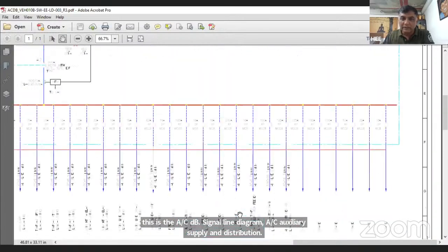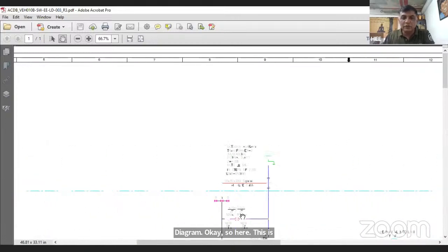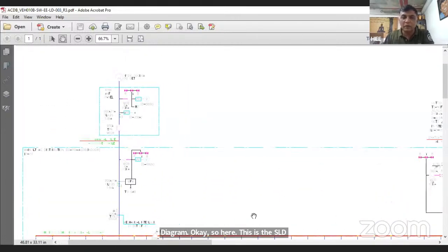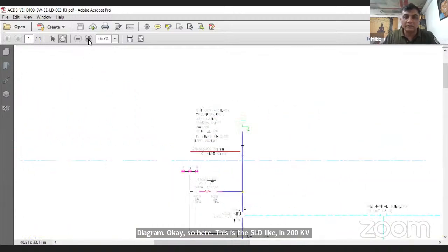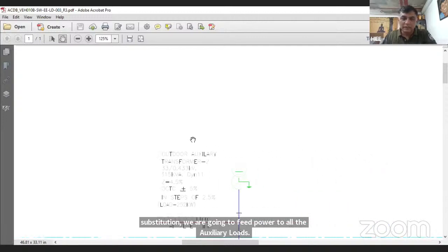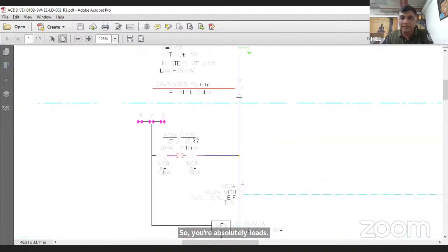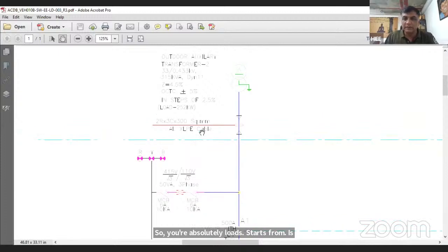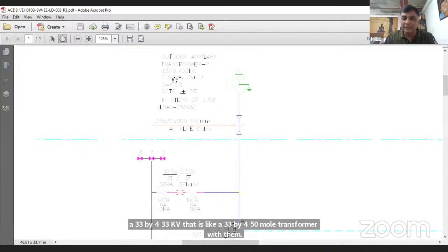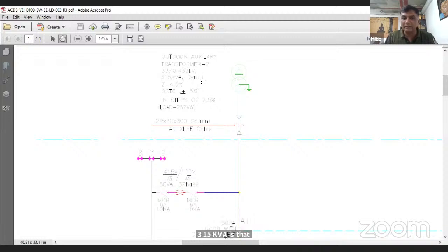So this is the SLD. In a 220 kV substation, we are going to feed power to all the auxiliary loads. Your auxiliary loads start from the ACDB. This is a transformer. The transformer is 33 kV by 415 volts, with 315 kVA as the transformer capacity, and DYN11 is the vector group of the transformer. So these are the transformer's technical specifications. From the transformer, we are connecting to the ACDB.